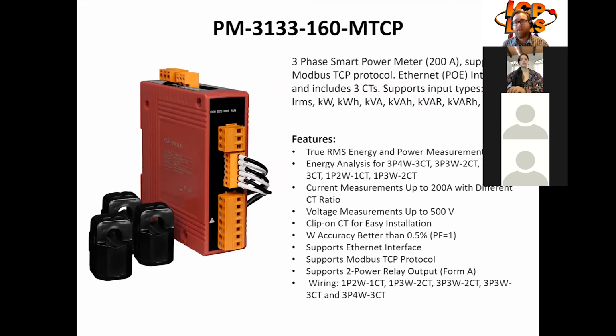Let's look at our next module, the PM-3133-160-MTCP. This is virtually the same module, except it comes equipped with a 16mm CT, max 100 amps, and communicates over Ethernet and Modbus TCP, as you can see on the screen. This makes it very useful if you already have an Ethernet communication network and want to get power readings from, say, a machine in a factory or an AC unit in a building. You can just plug this module right into the router.